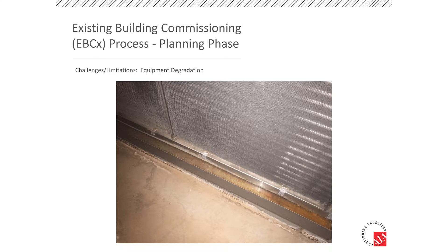These are steam dispersion tubes inside the air handling unit used for humidification. There's quite a bit of scale buildup on the nozzles for that dispersion tube. So if you have orifices that are filled in and you're not able to get that steam out into the airstream, you're probably not going to be humidifying as well as you need to be.